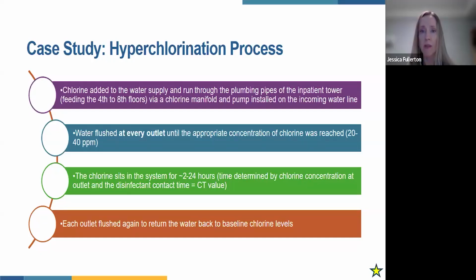Then once we had the chlorine in the system at the correct ppm, we needed to flush every outlet in our inpatient tower. Our inpatient tower runs from floors 4 to 8, and so this was upwards of 3,000 fixtures. Every faucet, every shower, every toilet, everything needed to be run to get that chlorine concentration to the outlet of every fixture. That chlorine then sits in the system for about 2 to 24 hours. The specific time is determined by the CT value, which is the chlorine concentration at the outlet and the disinfectant contact time. So there's no one size fits all here. You test as you go to make sure that you've hit that CT value.